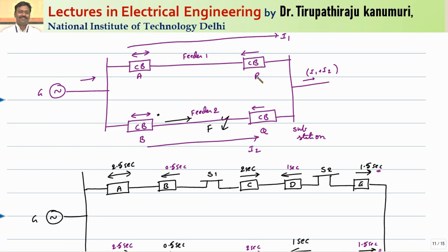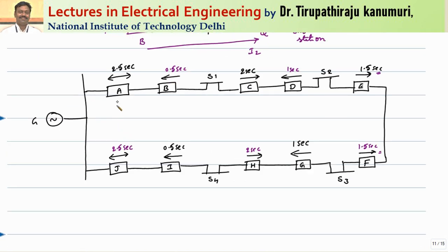For example, the relay at P will operate in the direction of the arrow only. Under normal conditions, the current direction will be from left to right, indicated by I1. But during the fault condition, let us assume some fault has happened here, so the direction of current will be like this - this is my direction of the fault current - and under these conditions, this relay will operate. Same thing is the case for ring mains. For ring mains also, at the sending end we go for non-directional relays, but all the remaining relays will be directional relays.